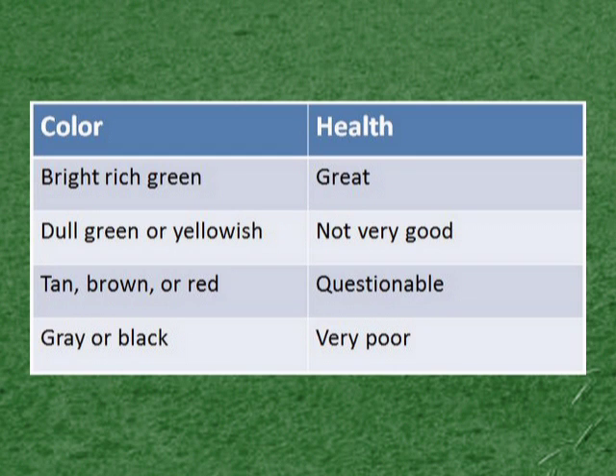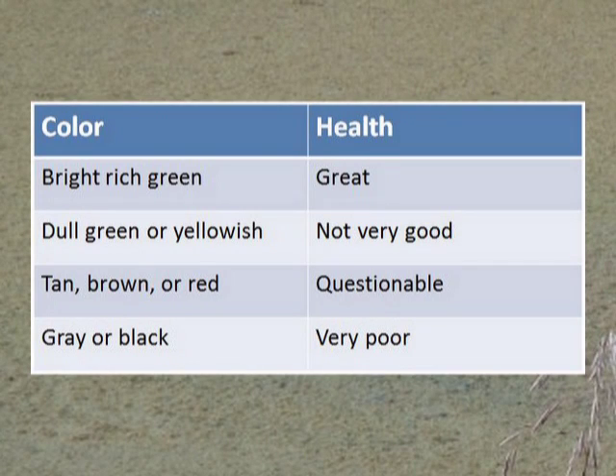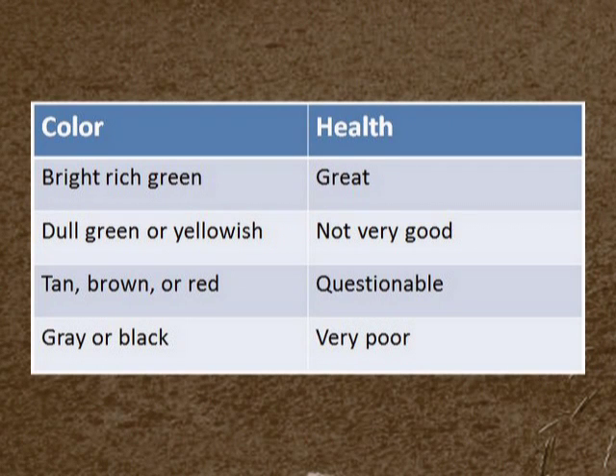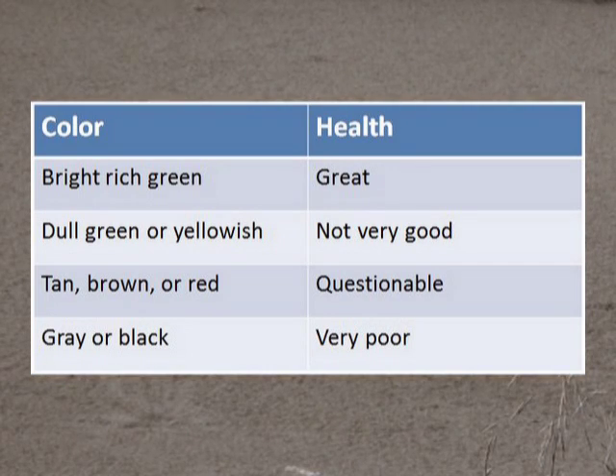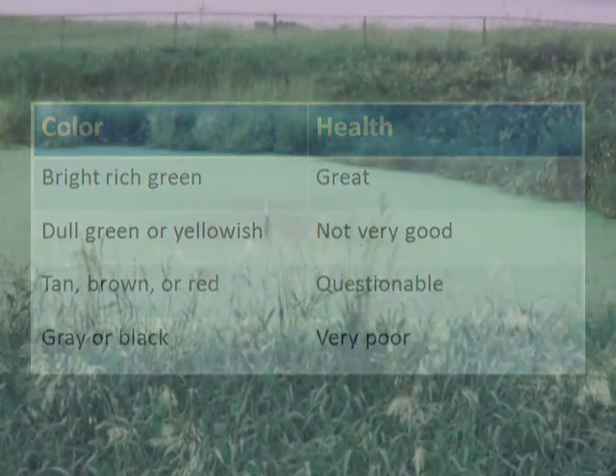Lagoon color is a good indication of the lagoon's health. The lagoon should be a bright green color because these green algae are an important part of the treatment process. Dull green, yellowish, tan, brown, or red colors show that conditions are not very good, and the lagoon has different algae that do not provide good treatment. A brown color may indicate that soil is eroding into the lagoon. Gray or black colors indicate anaerobic conditions may exist, so the lagoon is not treating wastewater well. Odors are probably present.